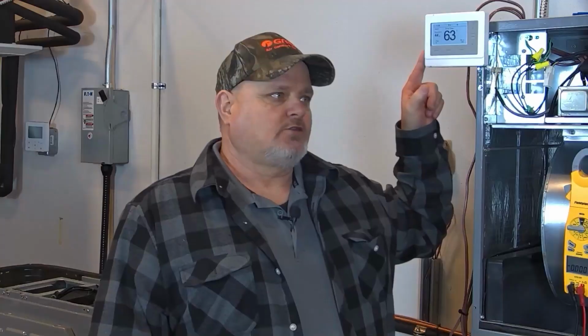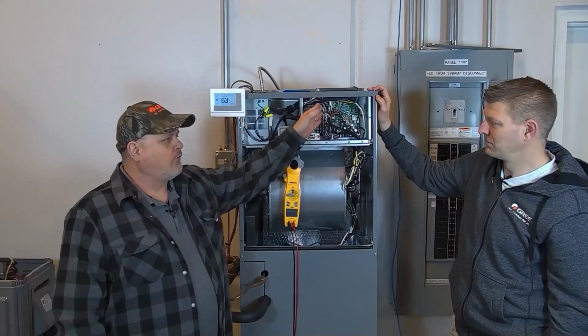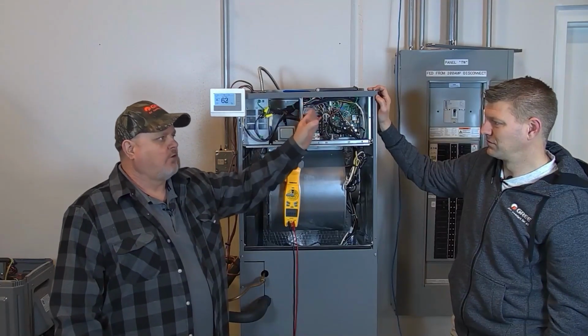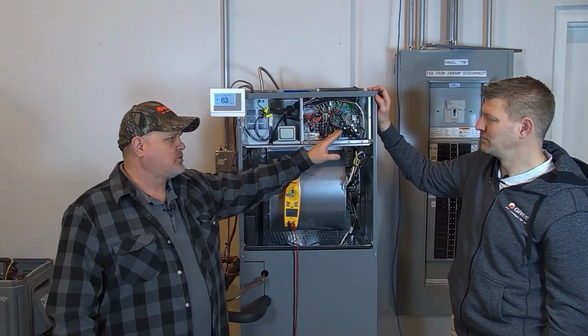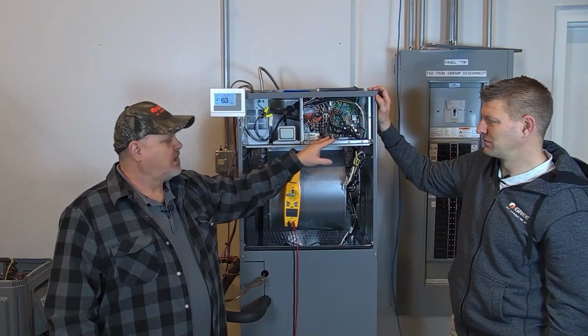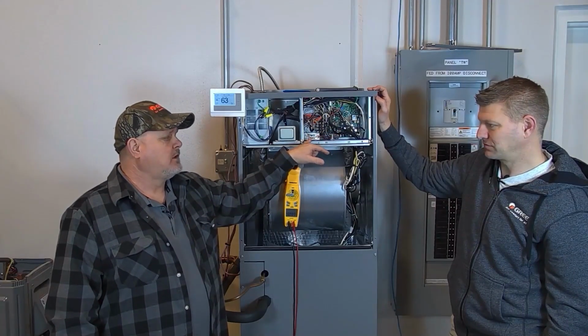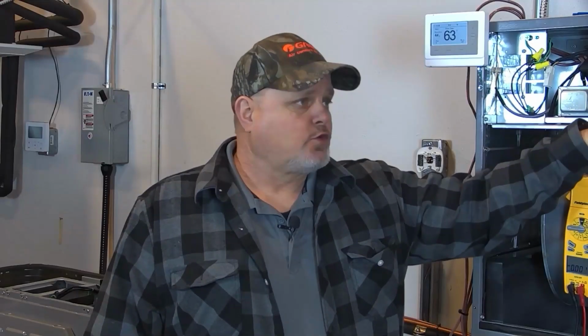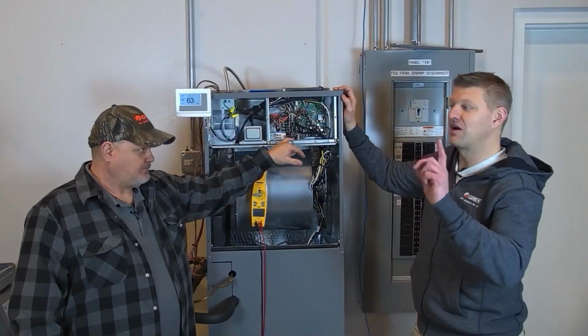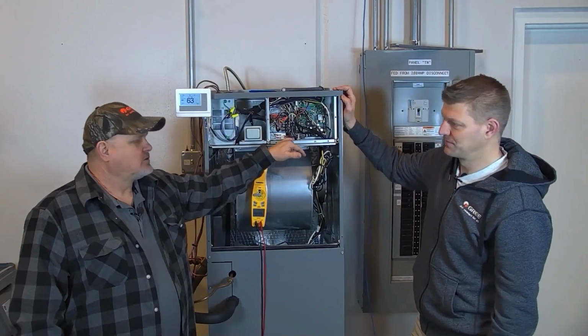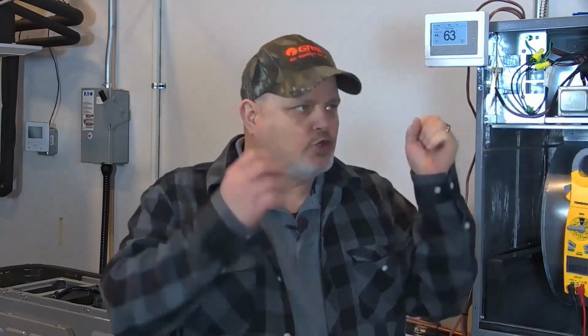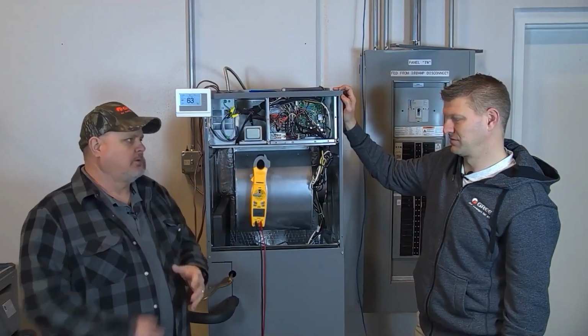And don't forget that if you're using RS-485, you've got to make sure you have a fresh fan call. Or if you're using 24 volt, you need to verify you're getting 24 volts to G and C. Another way you might want to test this is if you look at the service manual and set the dip switches. Even if you're using RS-485, you can disconnect your H1 and H2 for a minute. You can change that dip switch for 24 volt: SA1 number 1 to the on position. Jump R to G. Now you know you've got your 24 volts, and the test would be exactly the same.